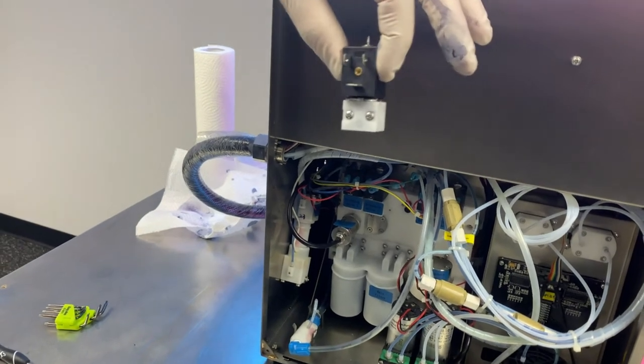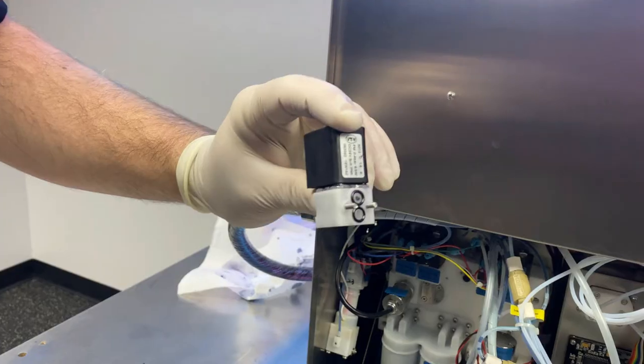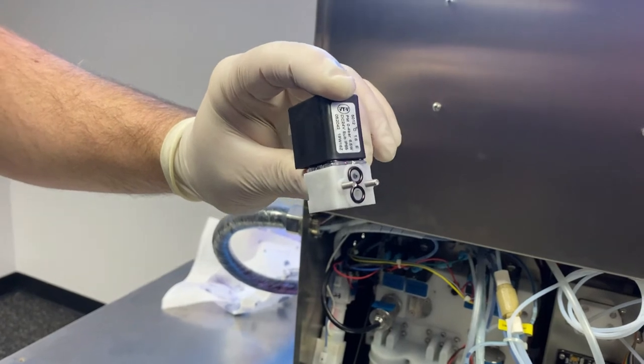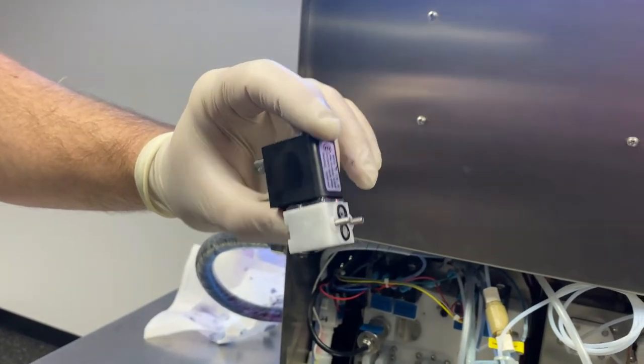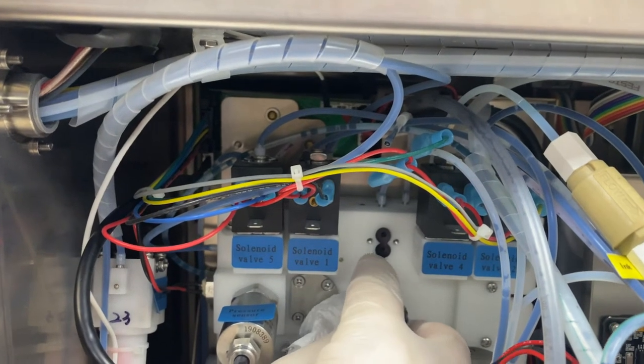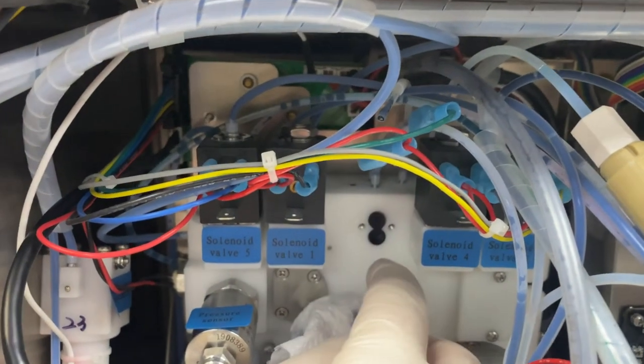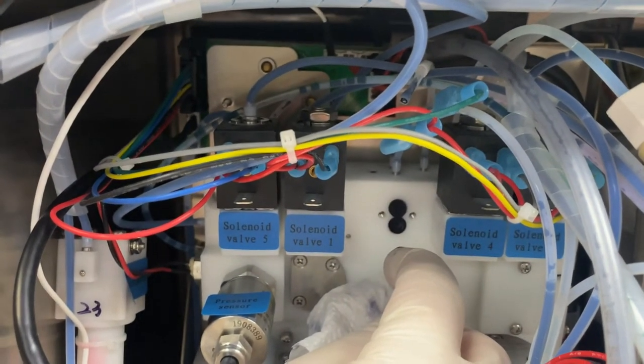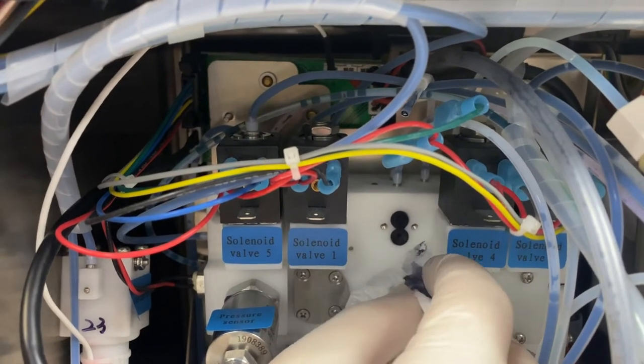This is how it should look. Again, I can't stress enough, be mindful of your O-rings, make sure those don't fall out while we reinstall the valve. When reinstalling, if there's a little bit of ink on the manifold, you can use a lint-free wipe and some cleaning solvent to wipe that off.